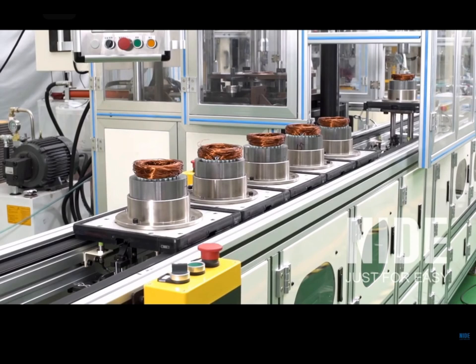That is called the insulation of the wire, or the insulation of the armature or field winding. It fails when too much current is flowing in the winding and it causes the insulation to melt. Once the insulation melts, the wires touch and start to short circuit, which will cause the wire to burn out.